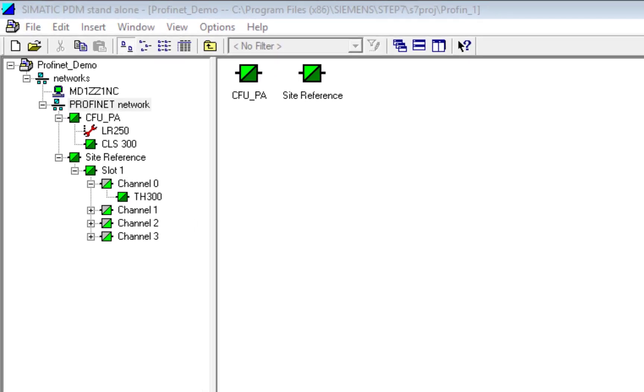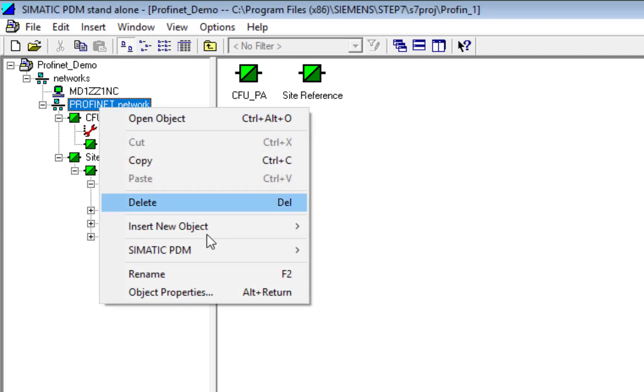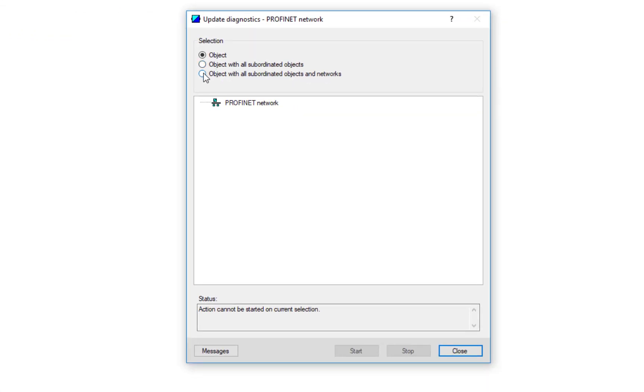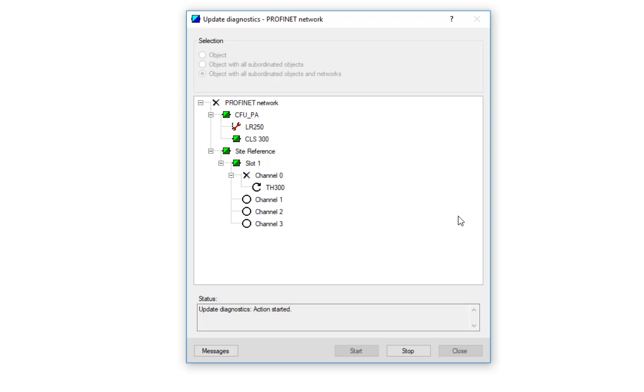So I now have a working project on PDM. So this allows me to select networks in one big chunk, and then I can update diagnostics for everything connected to that Profinet network. So rather than going to each individual instrument, I can status scan complete networks, IO, or individual instruments. And you can see in this case, I'm just selecting the whole network. So I want to see what the current status is of all the instruments on that network.